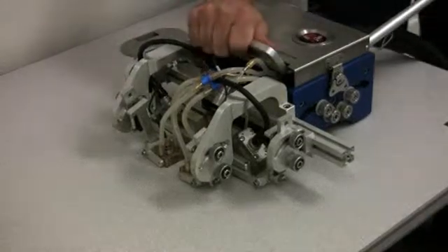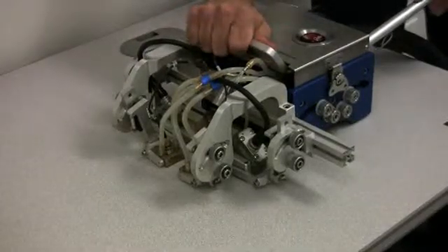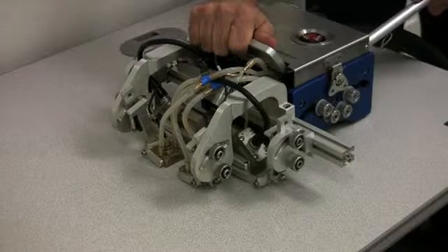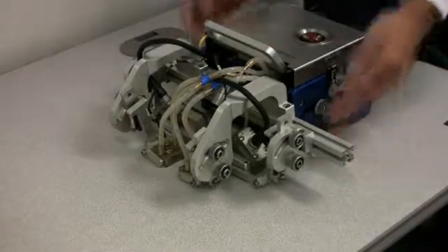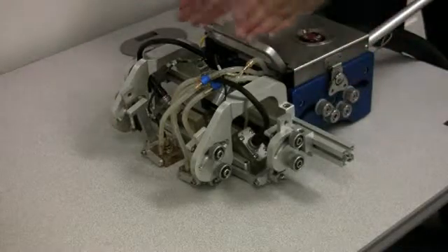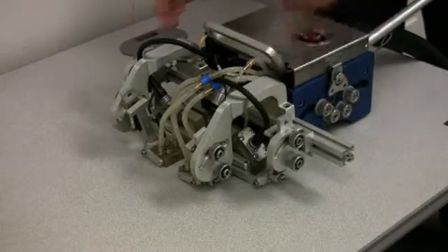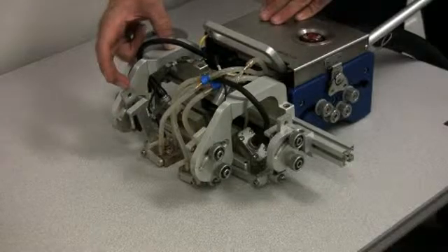Preparing the scanner for the pipe inspection requires making adjustments both for the diameter using these controls and for the probe position on the index axis in and out and taking a measurement of the distance between the probes.